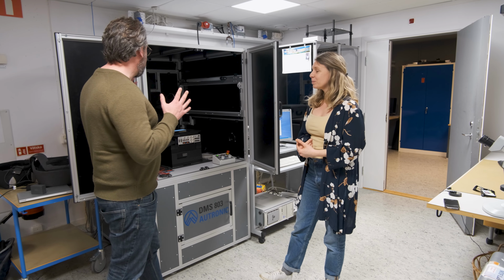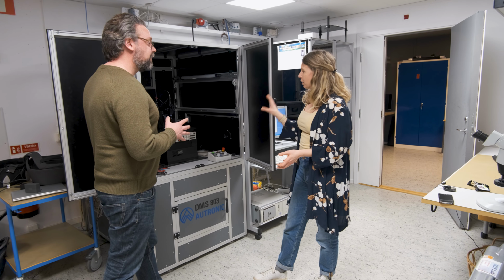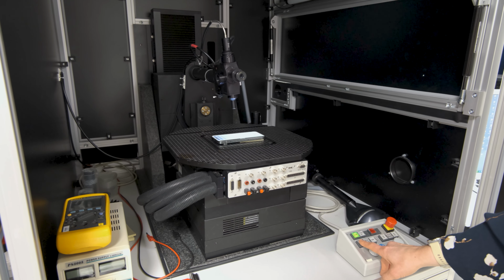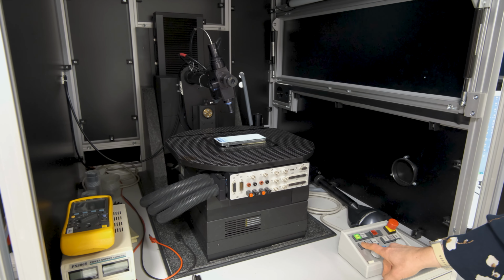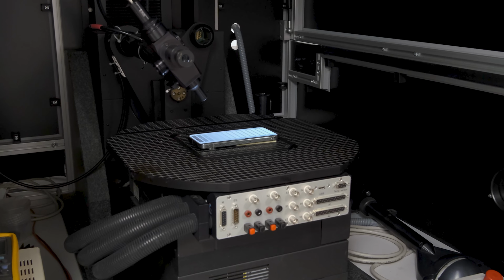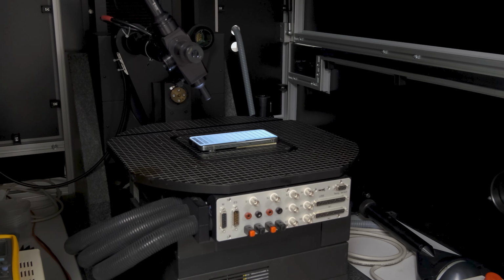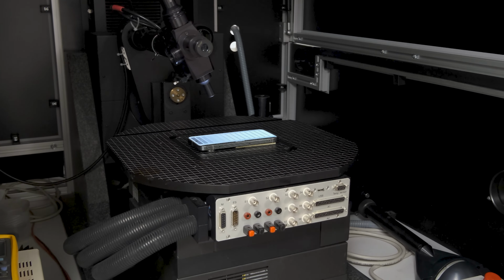Really cool. So what are we looking at here, Emily? So this is a major workhorse, our display measurement system, and it can measure emitted light intensity and color spectra. Okay. And from those data we can also calculate things like white point and contrast, and those are very crucial parameters for a display. And you see the arm there, it can move, and the table, it can rotate, so we can also measure from different viewing angles across the display.